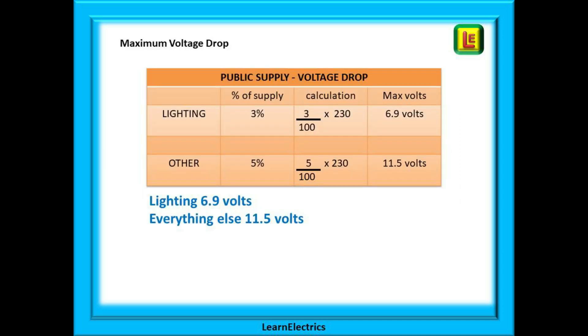We need to know the maximum voltage drop in volts, not in percentages. For lighting, three percent is found by dividing three by a hundred and multiplying by 230 volts, and the answer that pops out of the calculator is 6.9 volts maximum. Do the same for the other circuits and we have five divided by 100 and multiplied by 230, giving us a maximum of 11.5 volts for all non-lighting circuits. Now that we know the maximum voltage drops, we will have something to compare our actual results to.